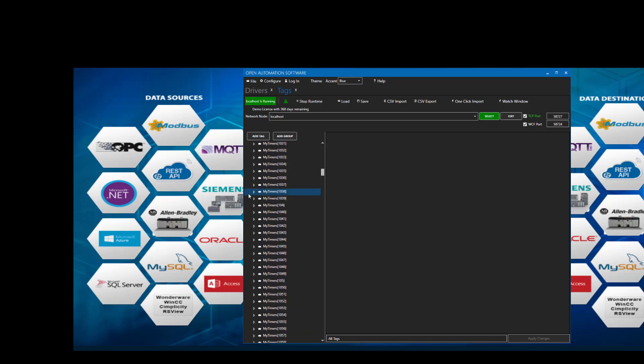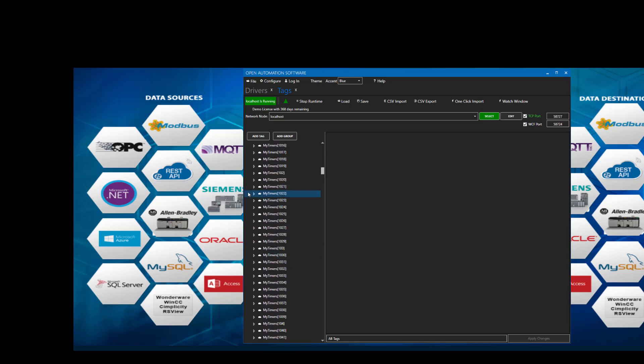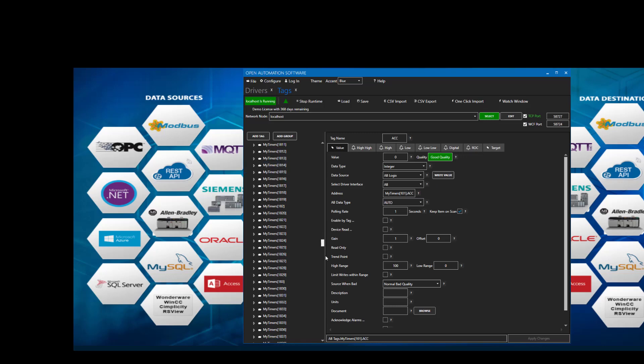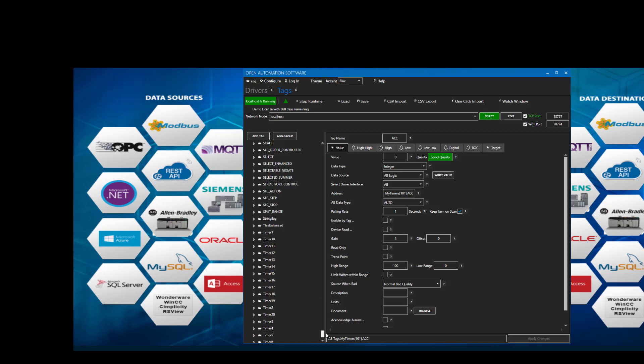Let's go back up and select a tag — let's go for the accumulated value, and you'll see that we have good data quality. The current value is zero. Let's go down and select another one. Let's select this timer, and that has an accumulated value of 349.